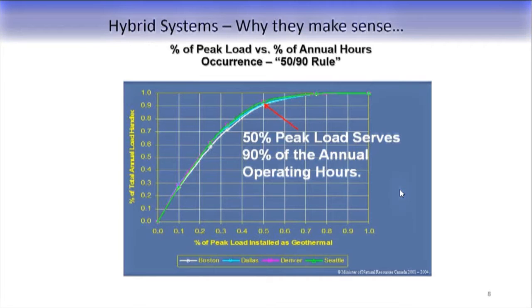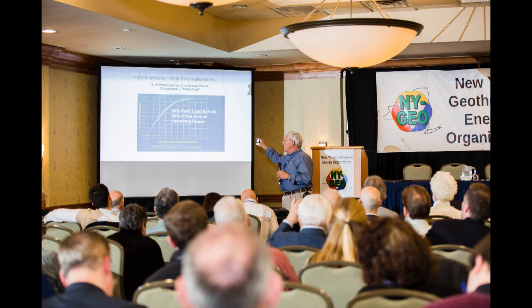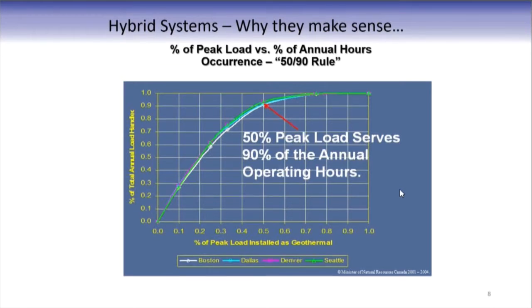The point of this is that 90% of the operating hours of the year, it will take less than 50% of the load of the building. Now what does that tell me about sledgehammers, non-controllable devices, non-VFD devices? It basically says, if you pay attention to this, it's true through the temperate zones of the world, not just the United States, not just New York, not just Utah, even works in Florida.